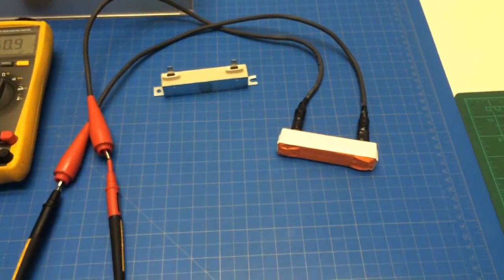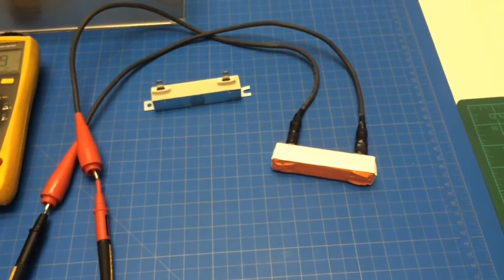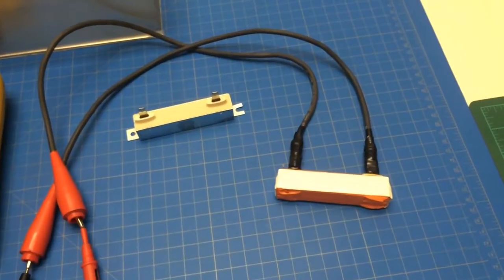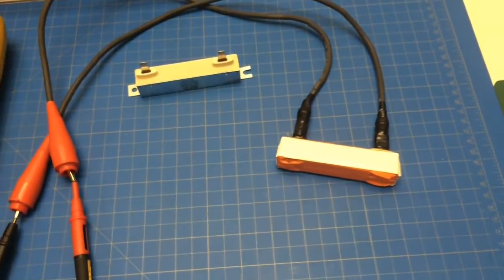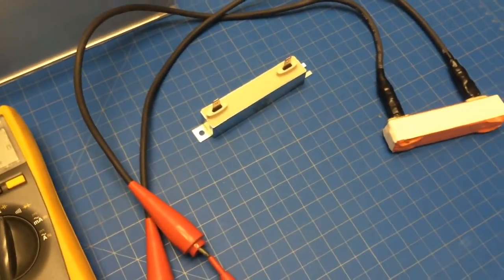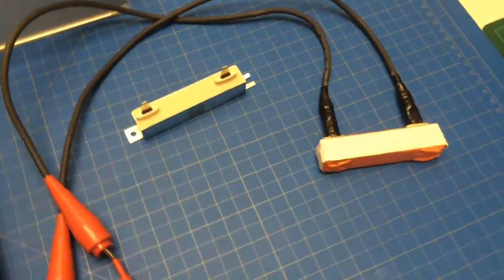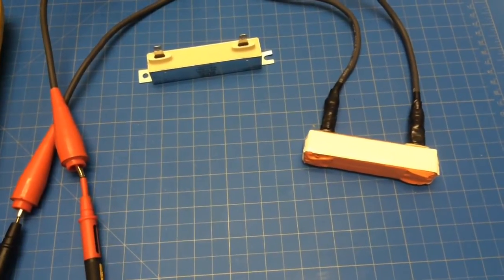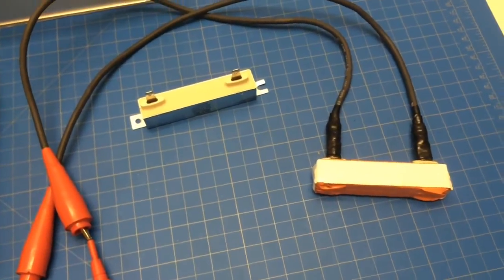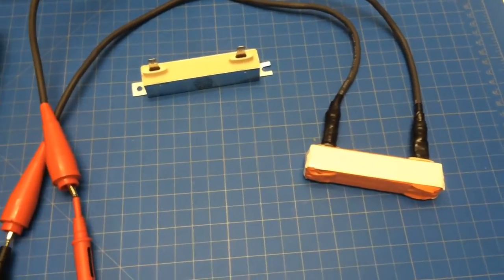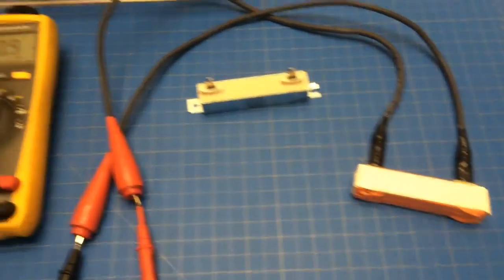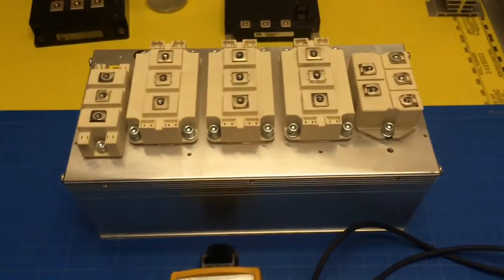If you don't soft start the capacitor bank, they can explode. They'll just charge too quick. So you have to put voltage on them through a resistance, let them charge up to about 75% or so, and then you can go ahead and short that resistor out with an IGBT contactor. You know, it's different depending on the application.